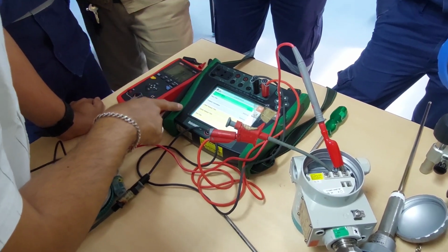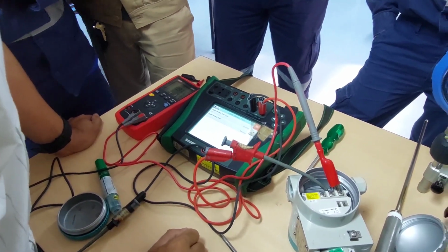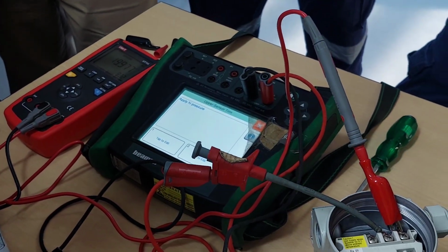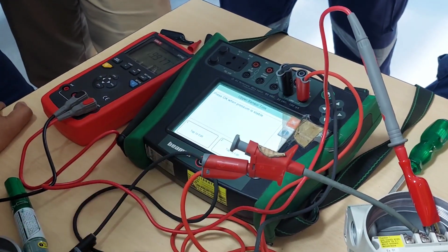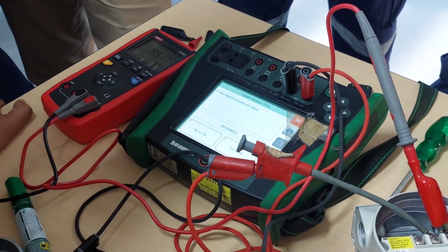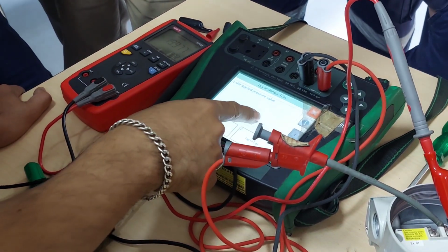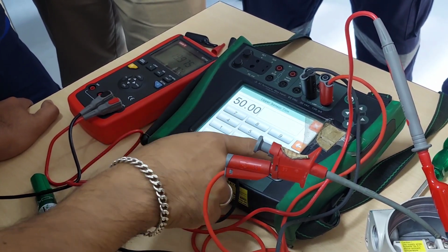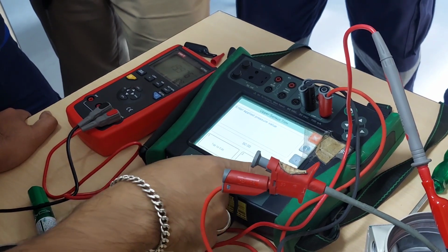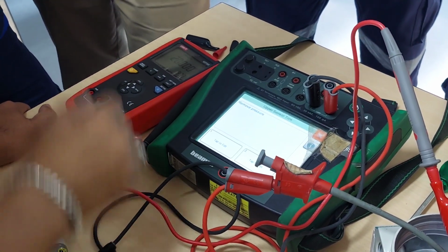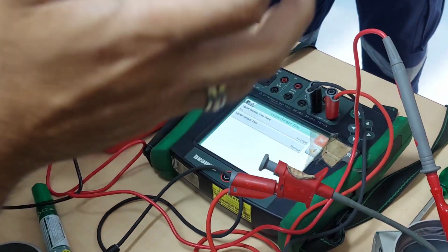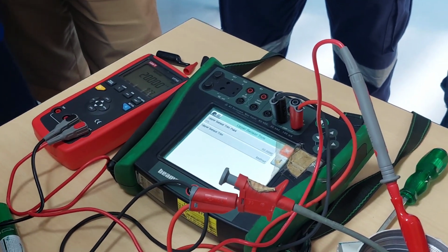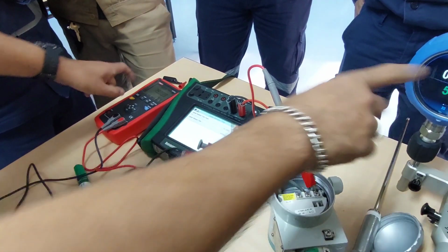So let me try to look at the sensor trim. Probably it's here. Apply high pressure. We already have high pressure 50. Enter applied pressure. So it's 50. There. So it doesn't have a separate analog output trim. It uses the upper sensor trim. Okay, so it's now equal.